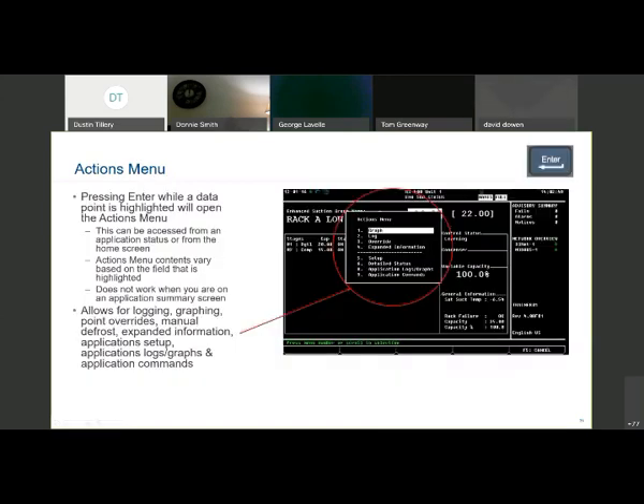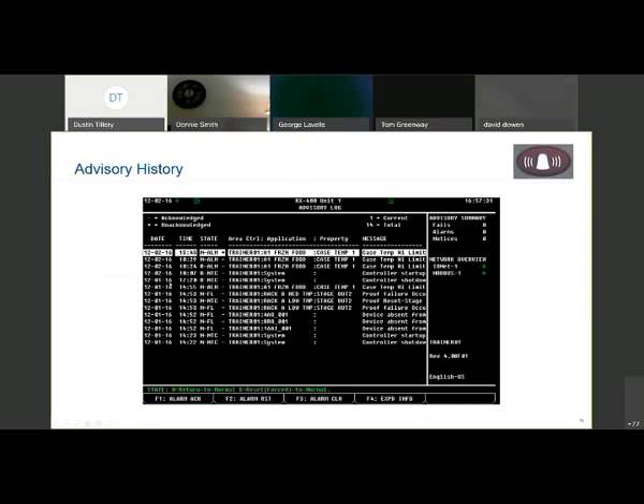If you will notice, let me go back one more screen. Down here on the bottom on our helpline, it tells us what these N's and these R's mean, right here next to our state. So an N means that it's returned to normal. The R means that it has been forced to normal. If you see one here with the asterisk beside it, it means that nobody has acknowledged it yet. That's even though it has returned to normal, nobody has gone up and said, hello, I know you're there, thank you very much, kind of a thing. All right. You have the dash, you know it's been taken care of. Somebody has seen it and acknowledged the alarm.